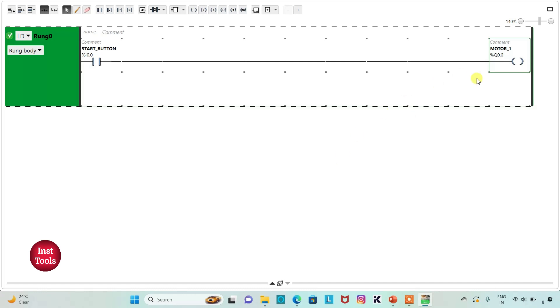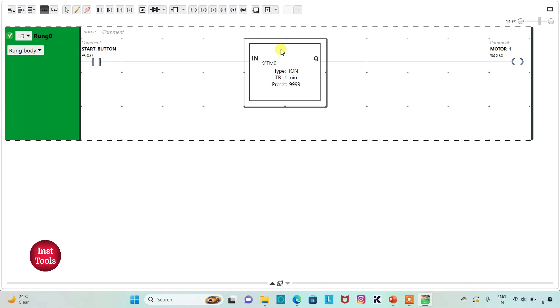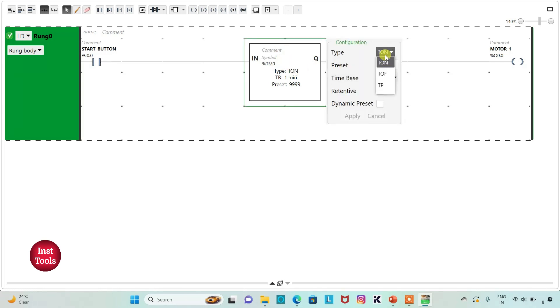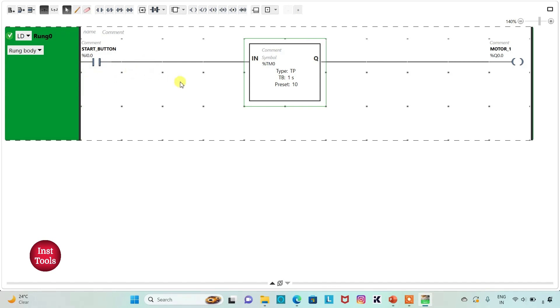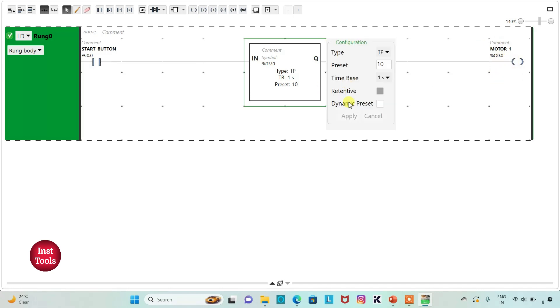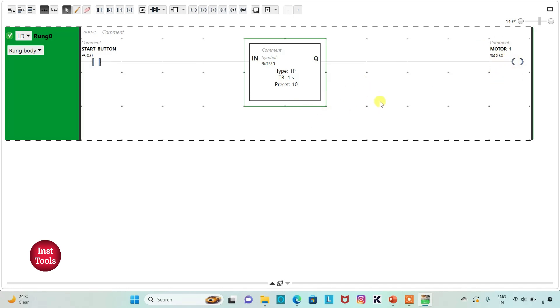The first stage motor should be on for 10 seconds, so I will insert a timer here and that should be TP. I will change the time base to 1 second and preset it as 10, then click Apply. So when the start button is turned on, the first stage motor will be on for 10 seconds and then after 10 seconds it will stop.